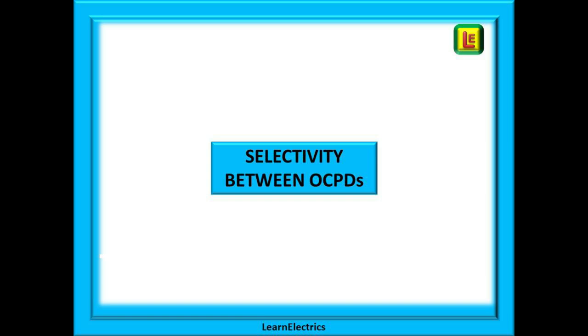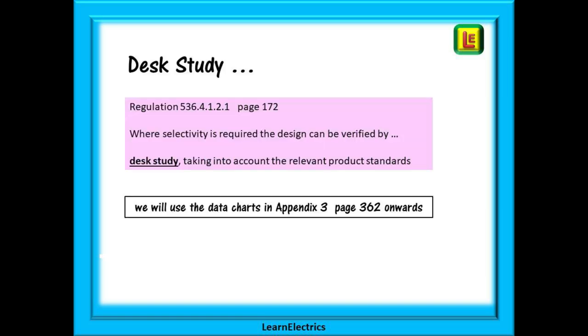Looking now at selectivity between over current protective devices regulation 536.4.1.2.1 on page 172 tells us that where selectivity is required the design can be verified by a desk study taking into account the relevant product standards. Desk study then is just sitting down with a pencil some data about the fuses or breakers and comparing the response times to overload currents. It's not complicated and we will use the data charts in appendix 3 on page 362 onwards.